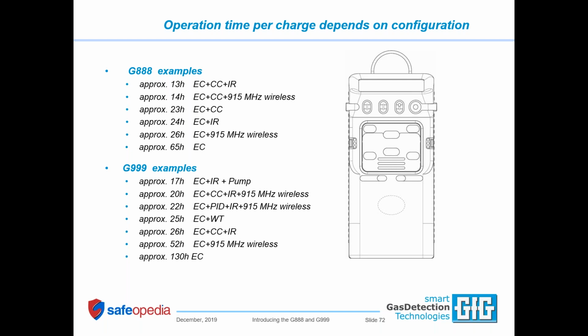The operation time per charge depends on the configuration of the instrument, but it's pretty amazing. A 888 with an electrochemical sensor, catalytic LEL sensor, and IR sensor, without the wireless module, gives 13 hours of continuous operation. With electrochemical, catalytic LEL, plus wireless, you get about 14 hours per charge. For a non-wireless standard 4-gas instrument with electrochemical oxygen, toxic, and standard catalytic LEL sensors, you get about 23 hours. With EC sensors only, you can get up to 65 hours per charge.